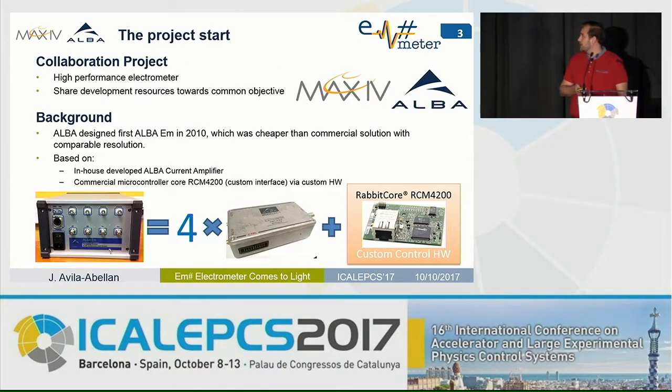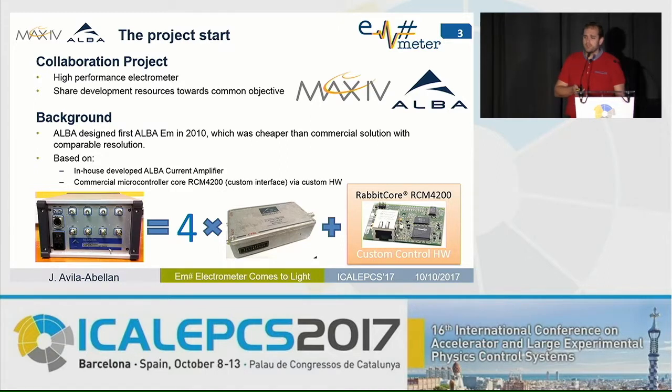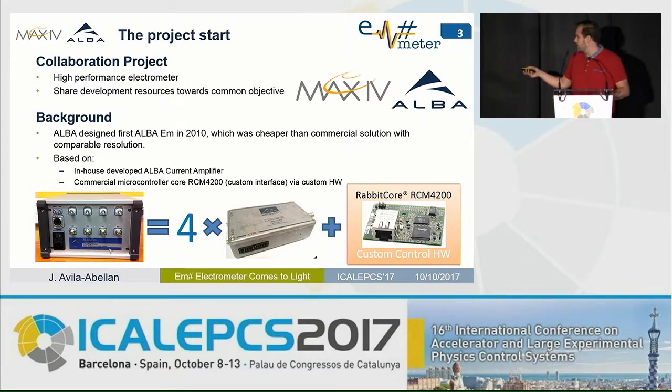This is a collaboration project between ALBA Synchrotron and MAX IV for the design of a high-performance electrometer, in order to share development resources towards a common objective. We didn't start from scratch, because ALBA had some background in electrometer design — the first version was designed in 2010. It was a mid-level electrometer, cheaper than commercial solutions with comparable resolution, based on four ALBA current amplifiers controlled with custom digital hardware using a commercial core with a custom interface and connector pinout.